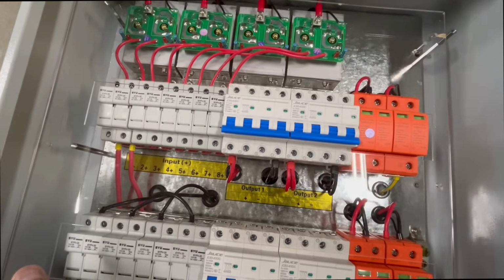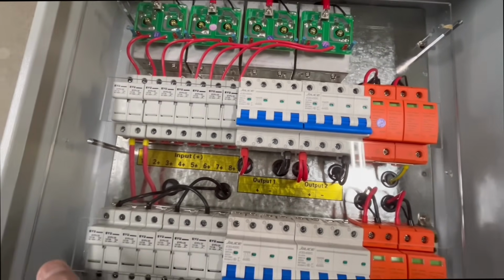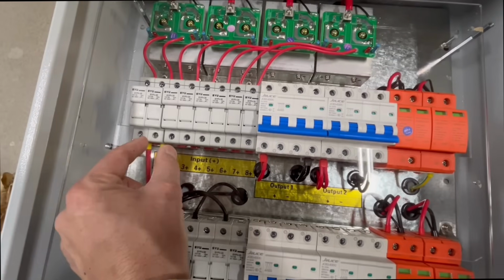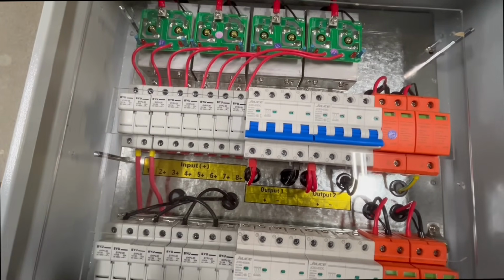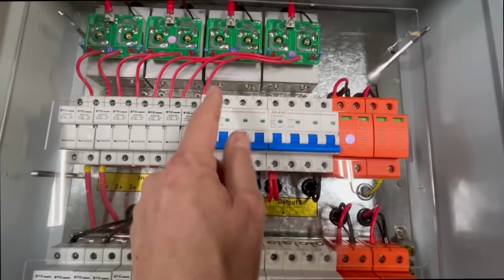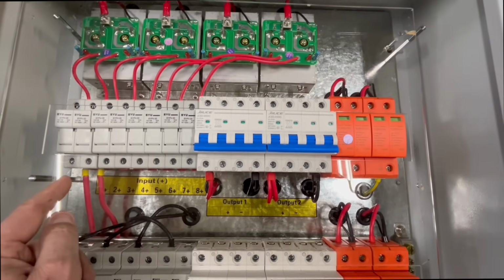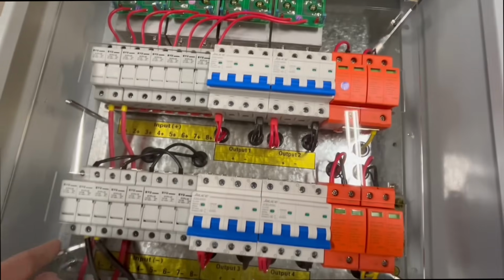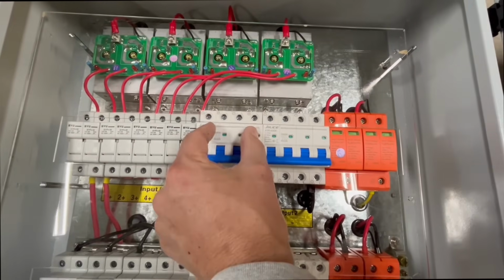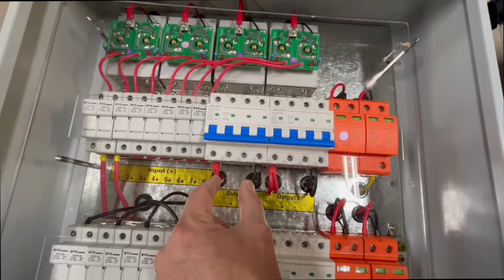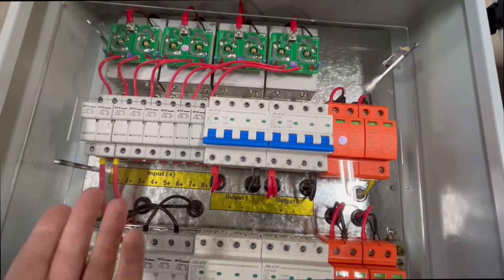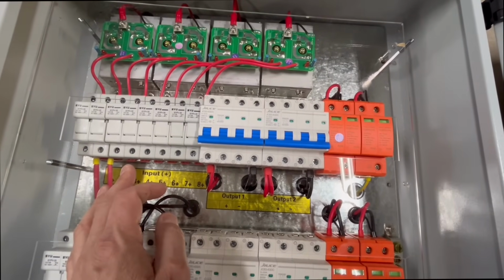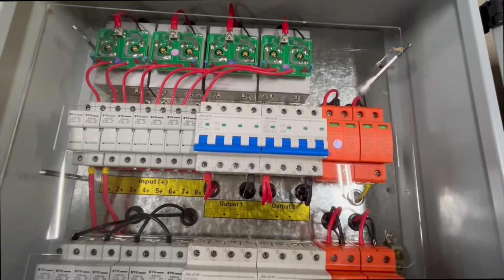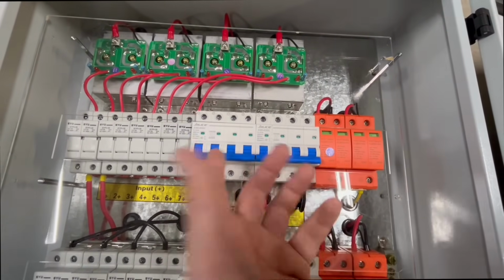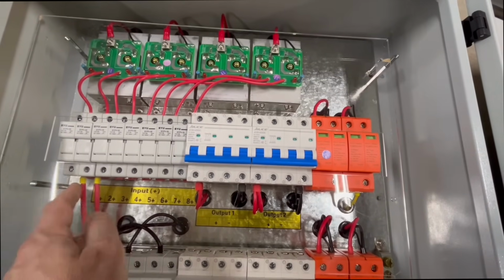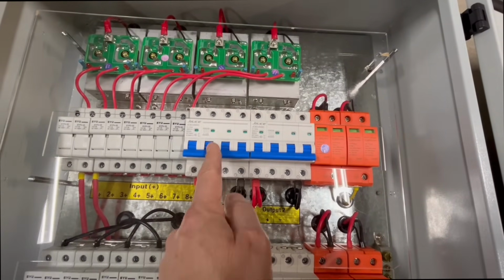So let's say you did it like I did it here with the 8-4 combiner box. So you've got these two strings coming in. That's not an issue. Now we know that there's going to be 8,000 watts because in our hypothetical strings, we have 4,000 watts and 4,000 watts, positive, negative, and they're going to be outputting right here at 8,000 watts because they've been combined together. But if you send that third string in, like I said, just for protection, that can output right here. And that is going to be 4,000 watts. So you've got 4, 4, and 4. So 8,000 on this one.